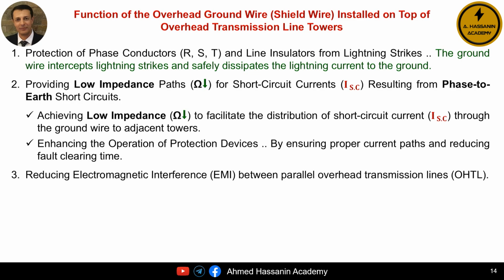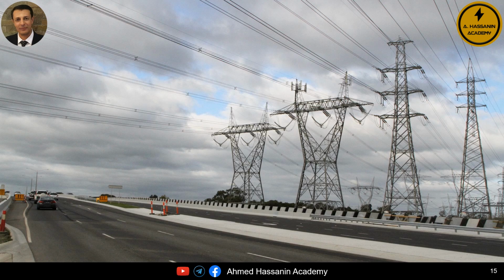Also, one of the functions and importance of the shield wire or earth wire or ground wire is that it reduces as much as possible the electrical interference or electromagnetic interference between the parallel transmission lines. Of course, we all know that each transmission line has a certain voltage, electrical power, and electrical current. This means that each transmission line has its own electric field and magnetic field different from the others. Naturally, there will be interference between these fields, and that is why the shield wire somewhat reduces this electromagnetic interference.